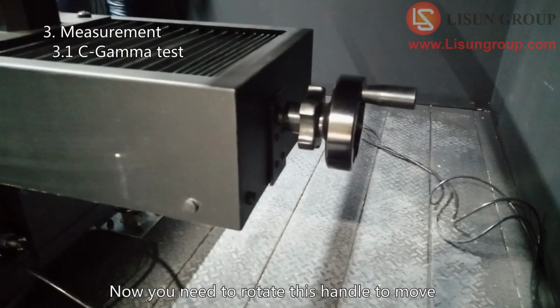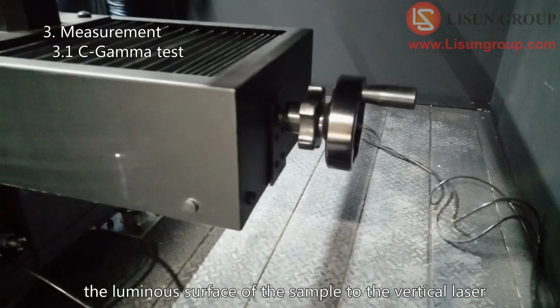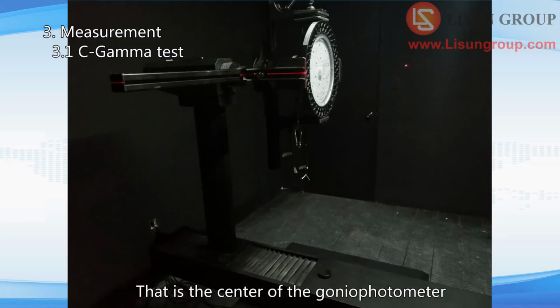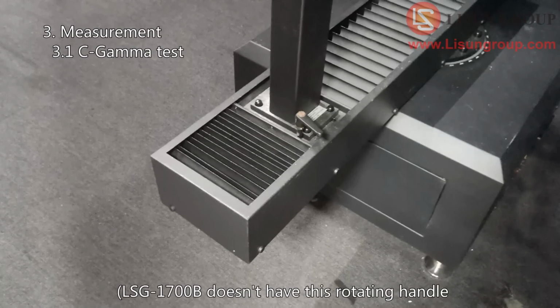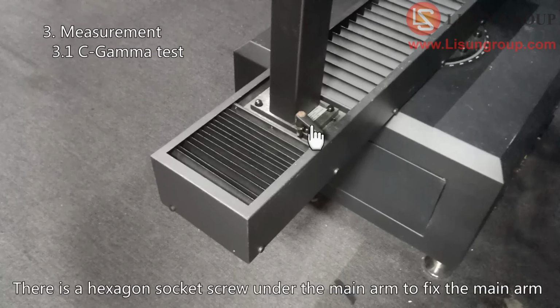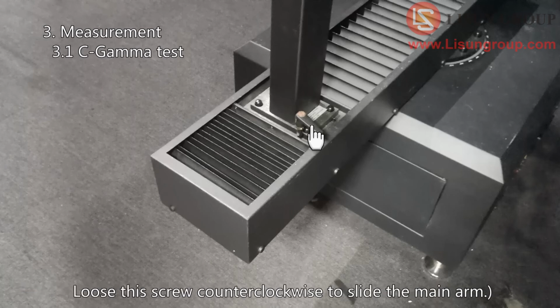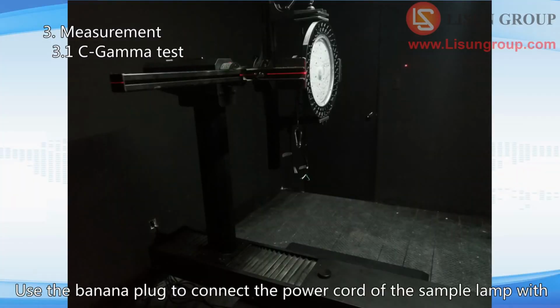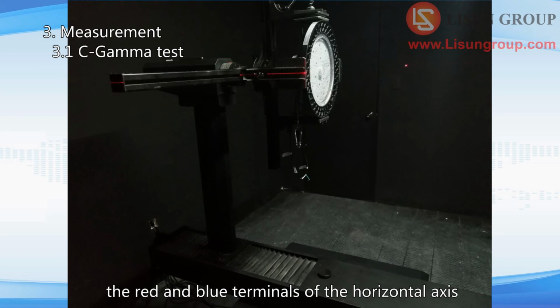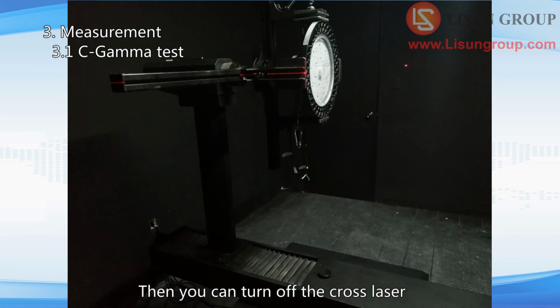Now you need to rotate this handle to move the luminous surface of the sample to the vertical laser. That is the center of the goniophotometer. LSG-1700B doesn't have this rotating handle. There is a hexagon socket screw under the main arm to fix the main arm. Loosen this screw counterclockwise to slide the main arm. Use the banana plug to connect the power cord of the sample lamp with the red and blue terminals of the horizontal axis. Then you can turn off the cross laser.